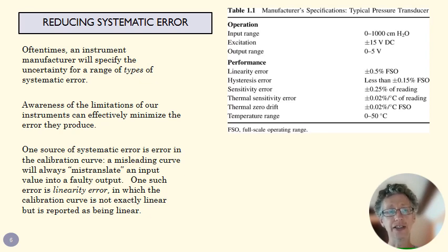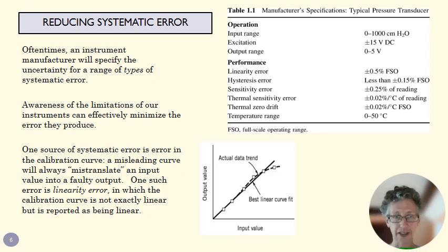Maybe the easiest to understand is linearity error, and linearity error looks like this if this is our calibration curve. So the dotted line here is our actual data, and then we use a linear curve fit to give us our calibration data. You can see that they don't match perfectly. So every time I measure here at this input value, I'm going to get a slightly wrong answer, and the same up here, I'm going to get a slightly wrong answer.